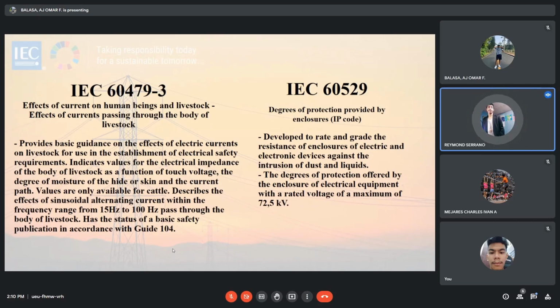The first numeral refers to the protection against solid objects. It is rated on a scale from 0, no protection, to 6, no ingress of dust. The second numeral rates the enclosure's protection against liquid and uses a scale from no protection to 9, high-pressure hot water from different angles. So next.